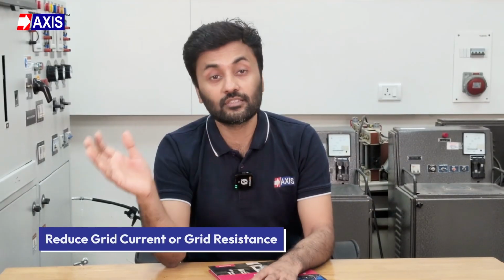To bring the ground potential rise down, you need to reduce either the grid current or the grid resistance. Reducing grid resistance is the practical approach. It is done by expanding the grid area, by adding more electrodes, increasing the depth of the grid conductors, or treating the soil to lower its resistivity. All of these measures increase the ability of the earthing system to dissipate fault currents safely into the earth.